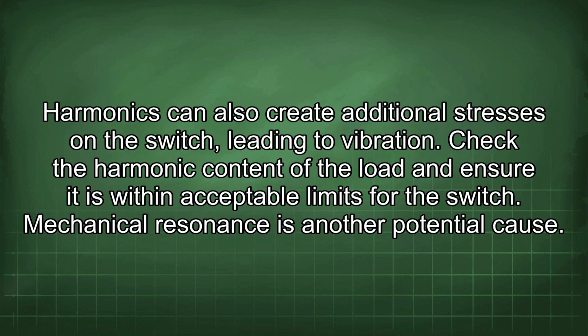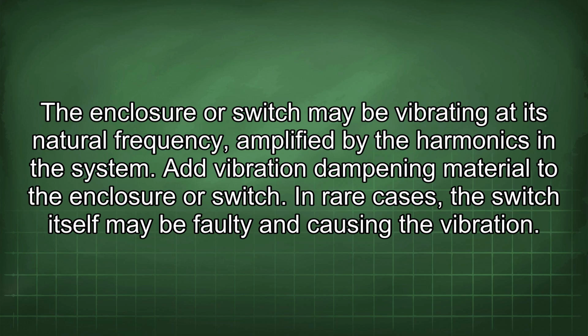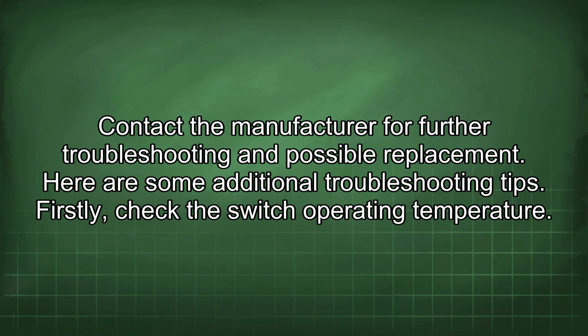Mechanical resonance is another potential cause. The enclosure or switch may be vibrating at its natural frequency, amplified by the harmonics in the system. Add vibration dampening material to the enclosure or switch. In rare cases, the switch itself may be faulty and causing the vibration. Contact the manufacturer for further troubleshooting and possible replacement.